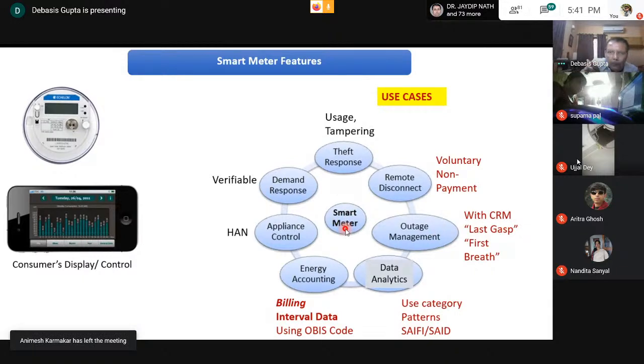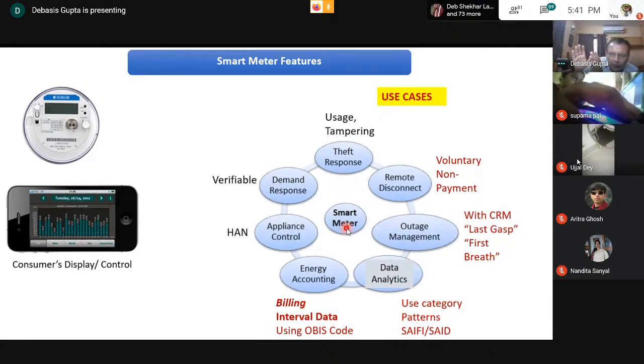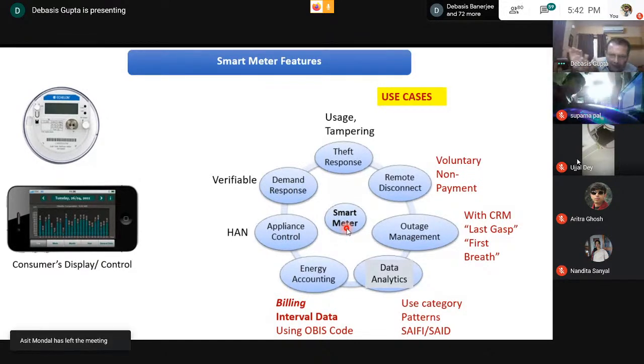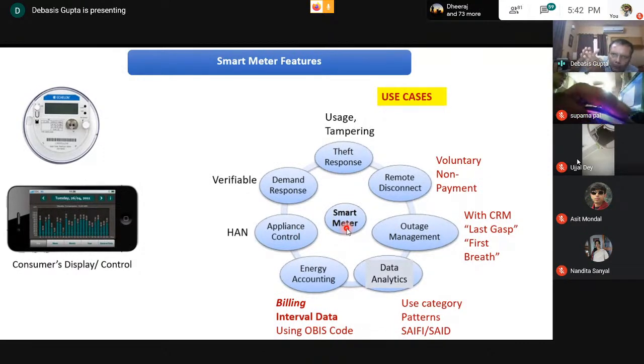This last gasp will go to the outage management system in your utility, which I showed you earlier. In the OMS system, all the last gasps will be plotted on a GIS. Then the ADMS software will take over, trying to find out, going back, where is the common fusing point, and whether the outage is only in that area.